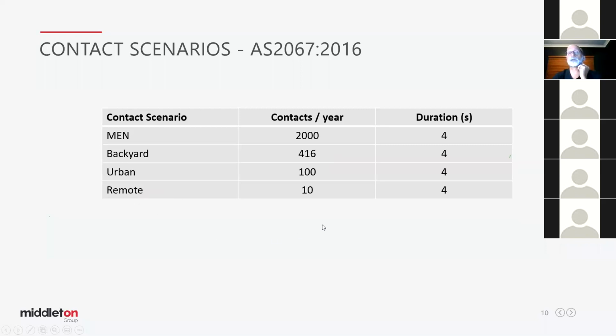And indeed remotely, so high voltage towers that are in paddocks and in the bush, we're less likely to be there as well, very infrequent. So the less likely you're going to be in contact with a conductive surface that may have a voltage created on it due to an earth fault, the less likely you are to experience a shock and the higher the voltage that is allowed there.